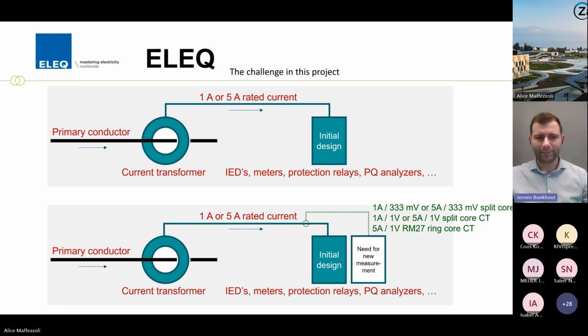What we really did here is try various solutions, split core CTs, 1A/333 mV or 5A/333 mV, but also ring core CTs, trying to achieve the desired wide range application and make sure we have the transfer accuracy we need while minimally impacting the existing burden, because we do not want to draw power away from the initial design intent, which is the protection relay currently there.